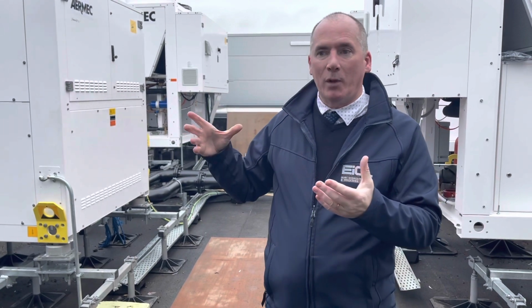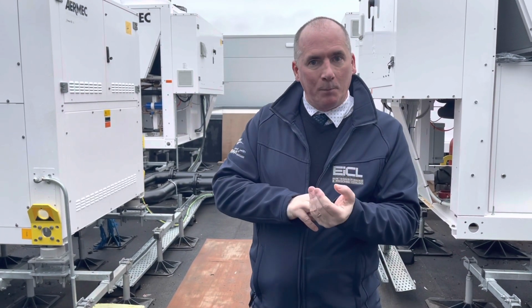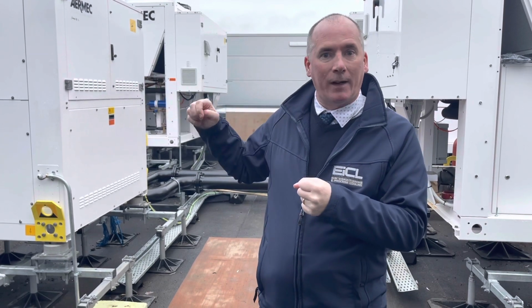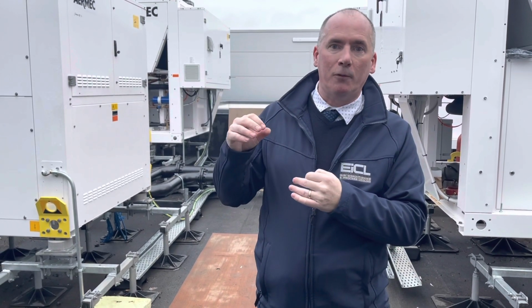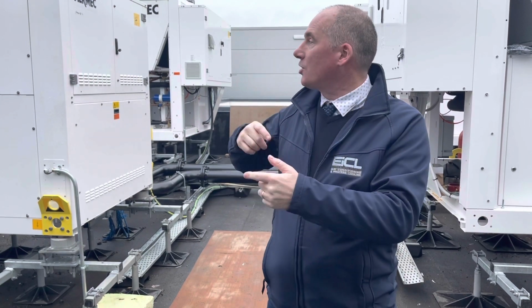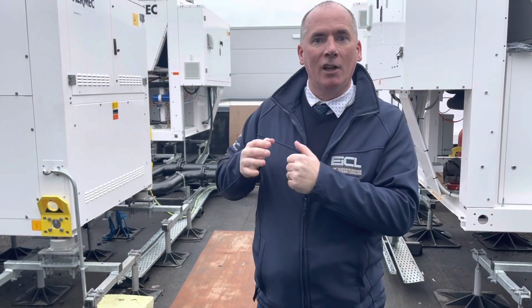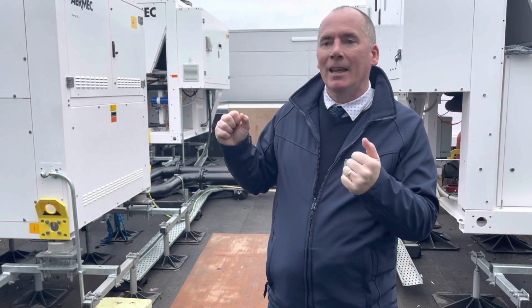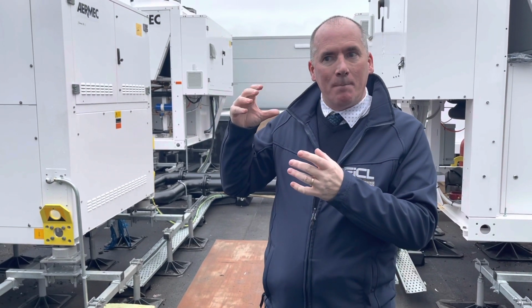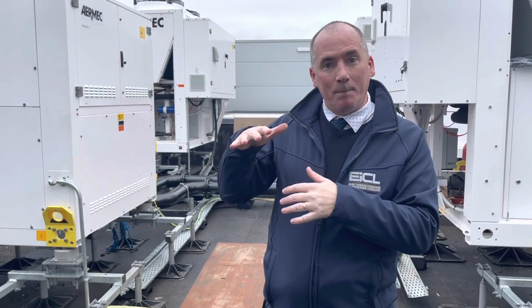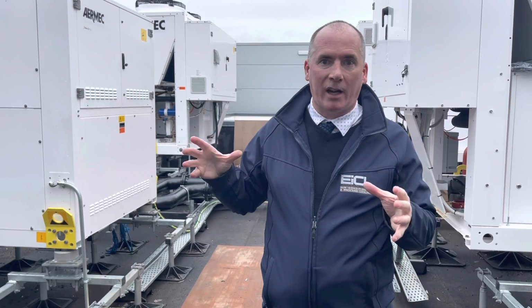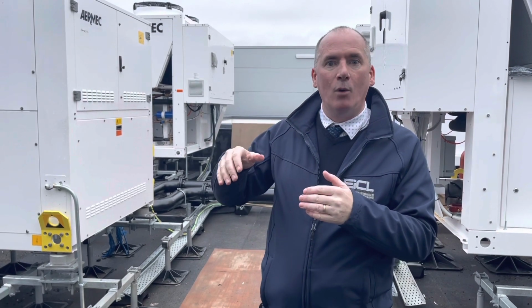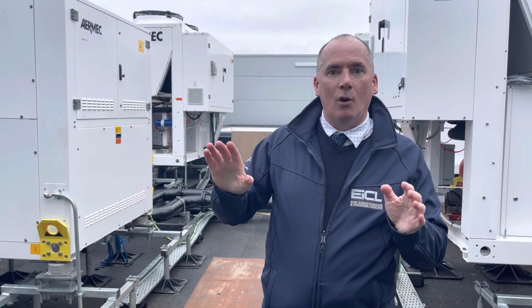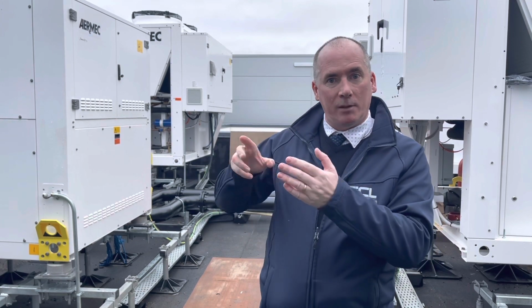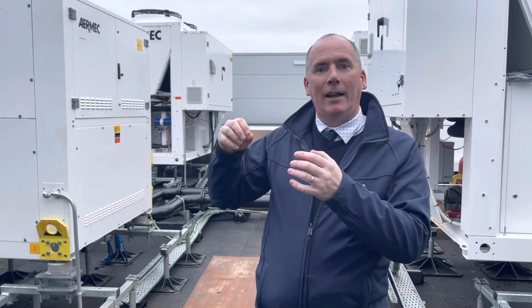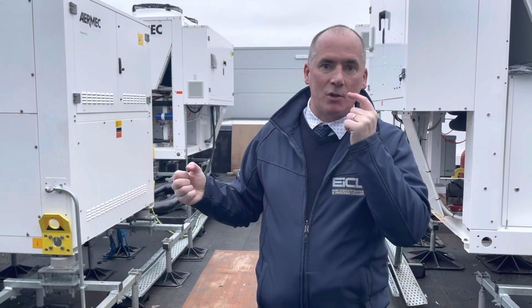And then of course we have a number of buffer tanks. The volume, by the way, in multifunctional heat pump systems is very important. Typically double what you'd be used to for a chiller or a heat pump, and that's because there's more modes of operation, more cycling, so the volume typically has to be that bit higher. So we have our buffer tanks. They're manufactured by Fiorini and they're manufactured with baffle plates, which is very important. They're not just a box standard buffer tank, so we direct the flow to where it needs to go. The cooling is directed straight to the outlet from the buffer tank, and it's the same situation with regard to the heating.